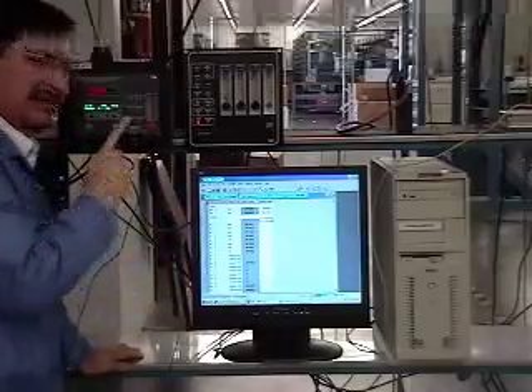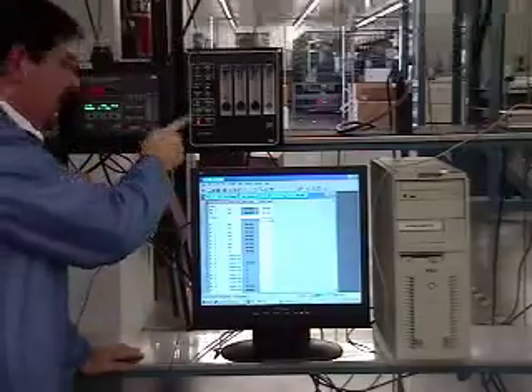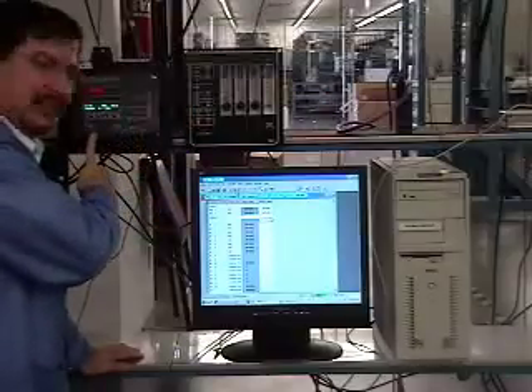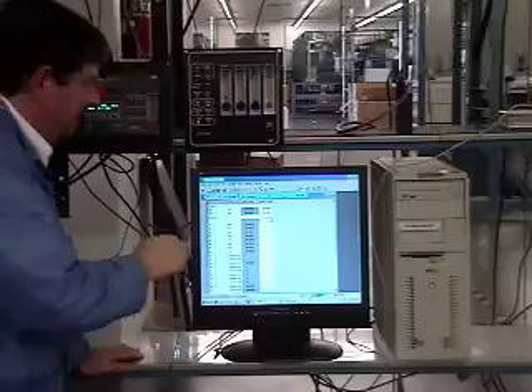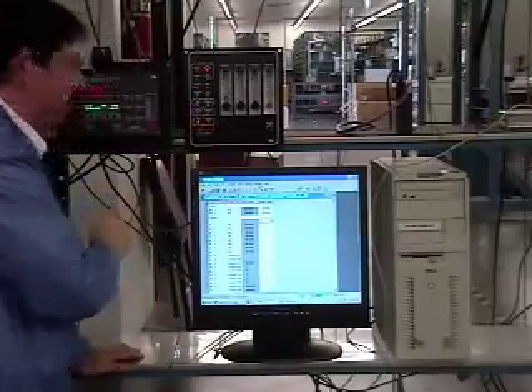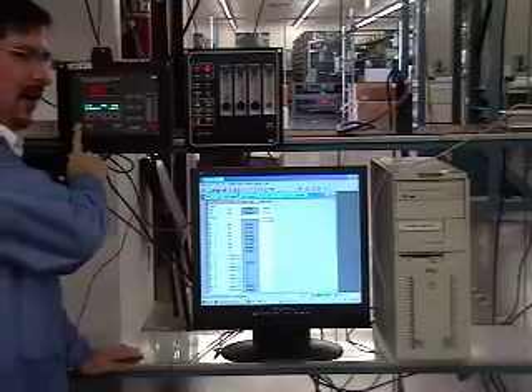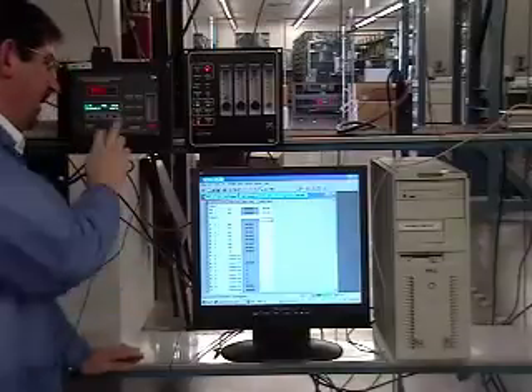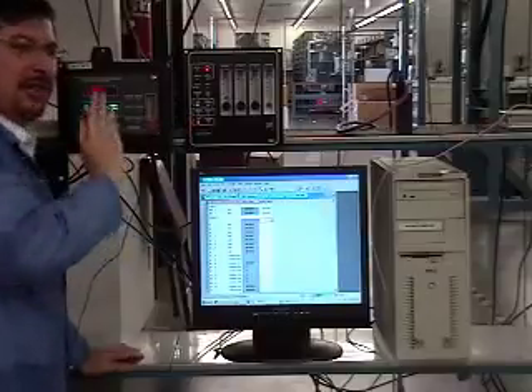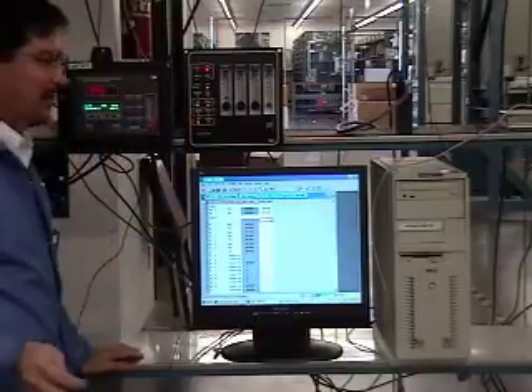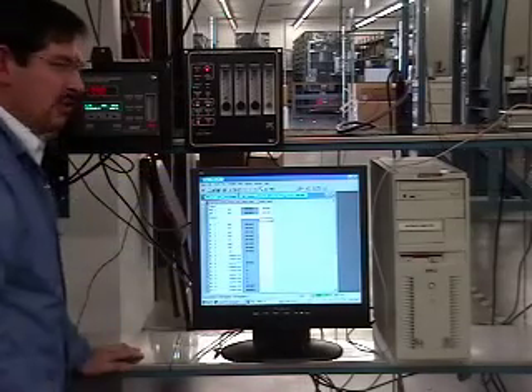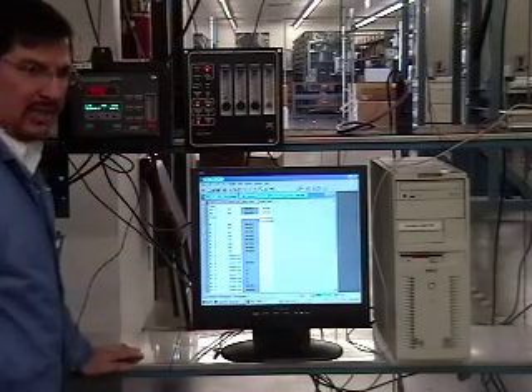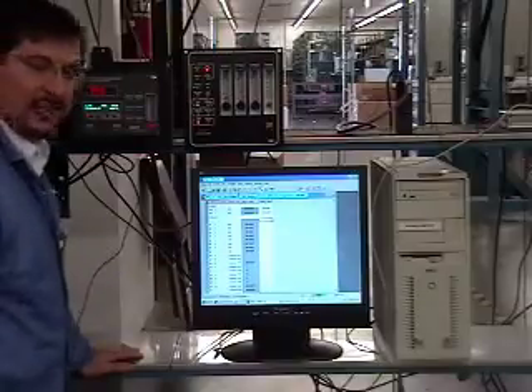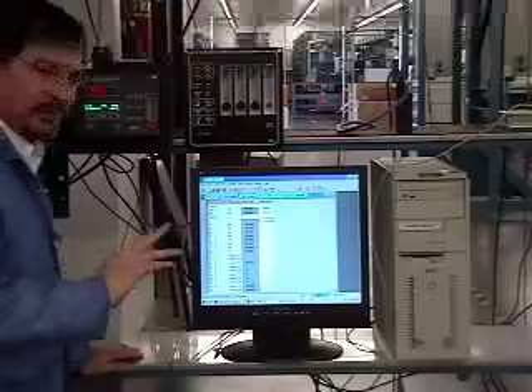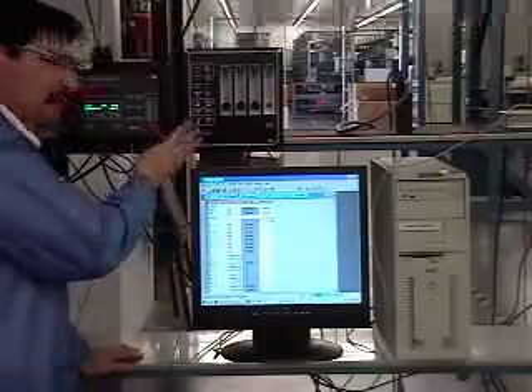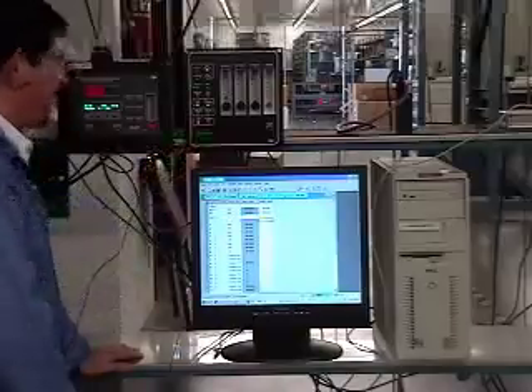But now, before I go to the next one, remember what happened in manual override. When I flipped to the high calibration gas, the analyzer did not go into span. And now when I do that, it will go into span. Because now we are not doing a manual override, we're doing a computer override. And what we're telling the instrument is we do want to calibrate. This is when you don't have a Step 7. So computer override is when you don't have a Step 7, you don't have a network. You just want to control the BB1 through some digital contacts or relay contacts. So if you have a PLC with contacts, and don't have a Profibus network, then you can use this computer override to control it.